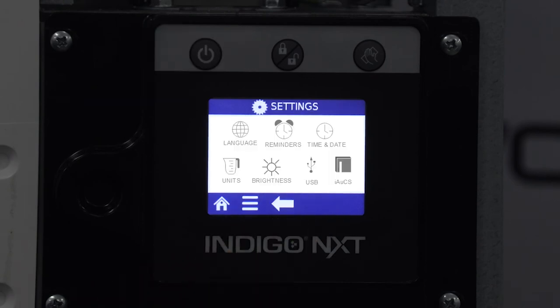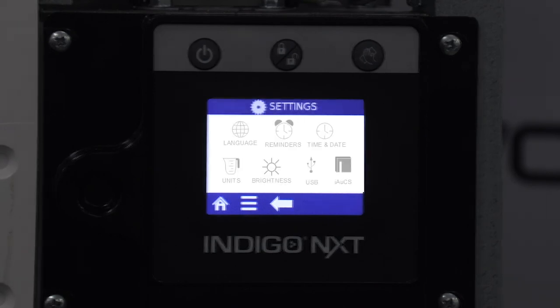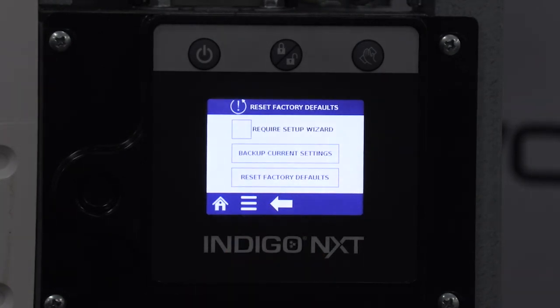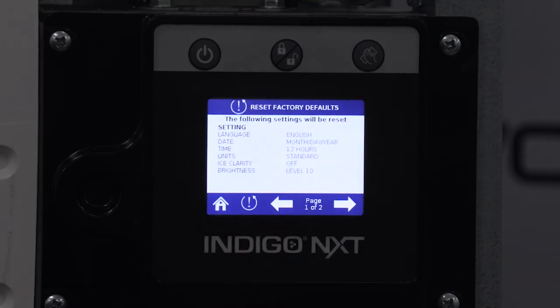The iAuCS icon is only visible if iAuCS is detected by the IndigoNext control board and is used to set the frequency of the cleanings. The last icon in the main menu is factory reset, which is the location to reset the install wizard, backup current settings, and reset factory defaults. When the reset is activated, the control will change the settings to the following: language to English, date to month/day/year format, time to 24 hours, units to standard, ice clarity to off, and brightness to level 3.